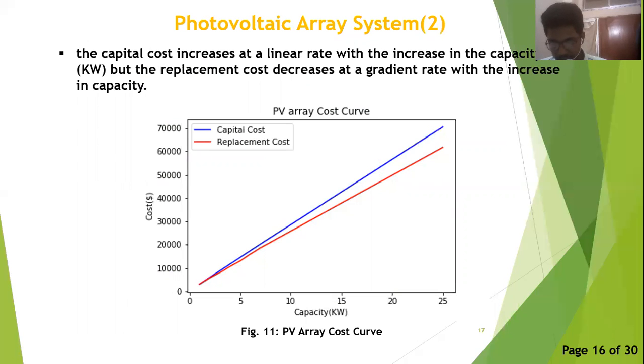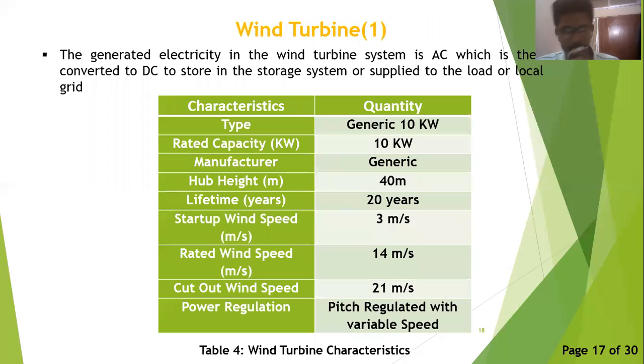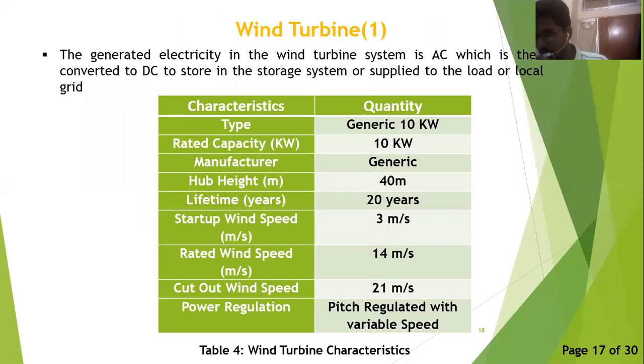The PV array cost curve is shown in this figure. The capital cost increases with the increased PV array capacity in the system, and the replacement cost increases at a graduated rate with the increase in capacity. The wind turbines used in the system are generic 10 kW wind turbines with a rated capacity of 10 kW and a hub height of 40 m. It has a start-up wind speed of 3 m/s, rated wind speed at 14 m/s, and cut-out wind speed at 21 m/s.